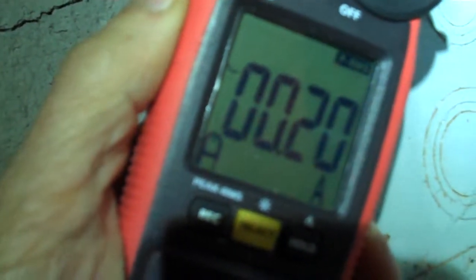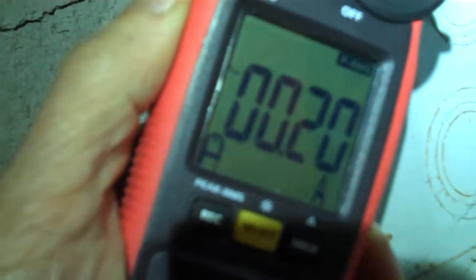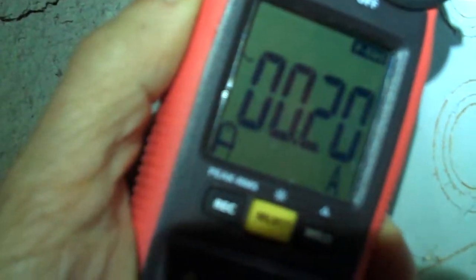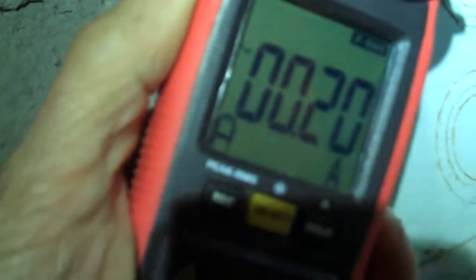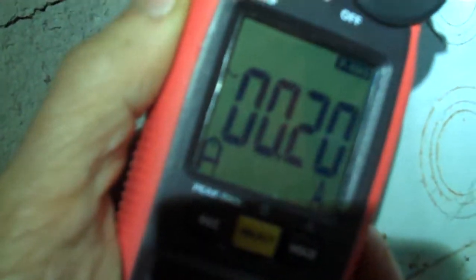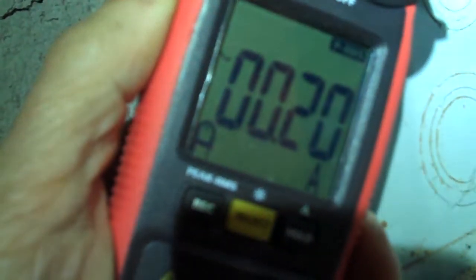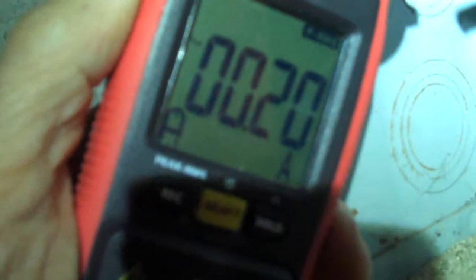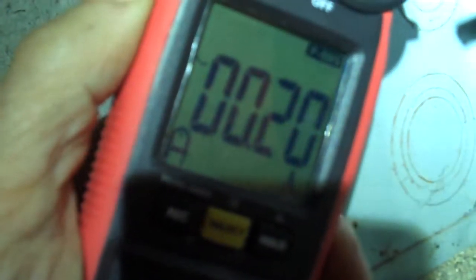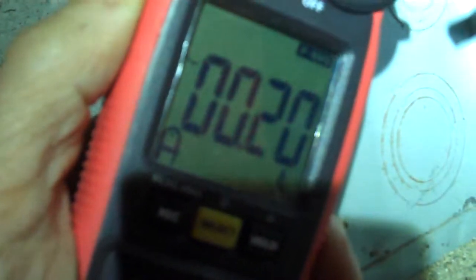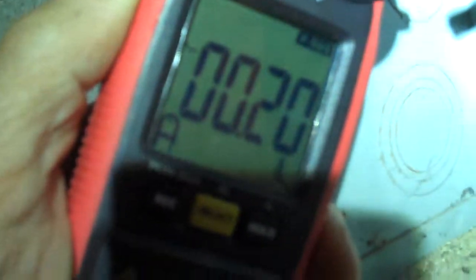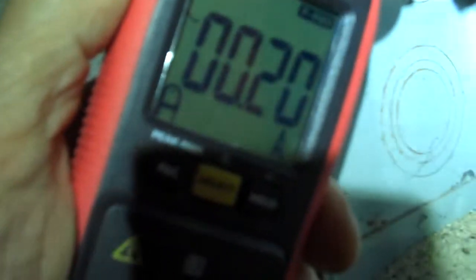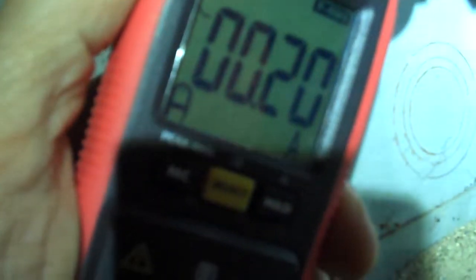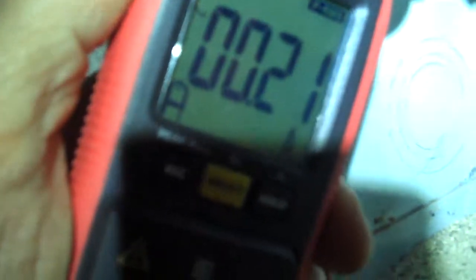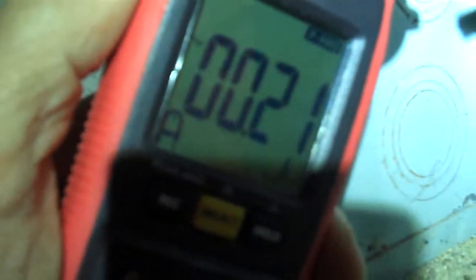Now the eone pump is spec'd for a starting wattage of 6,500, and it's spec'd for a starting current of 30 amps. And if you draw 30 amps from 240 volts, that comes out to 7,200 watts, which would be the wattage if you drew 30 amps straight into a resistive load. But in this case, the load is not entirely resistive. It's partially inductive, and you can draw 30 amps and dissipate less than that because the power factor of the load is not equal to 1. A resistive load would have a power factor of 1. The power factor of this load appears to be around 0.9, because if you use a power factor of 0.9 and you draw 30 amps, that will give you the 6,500 starting watts.